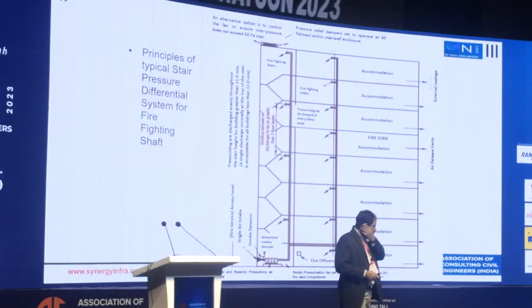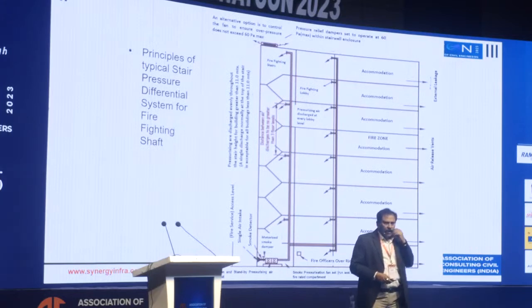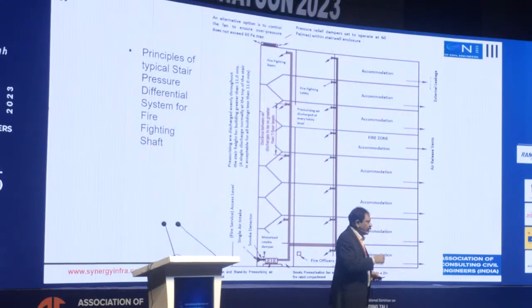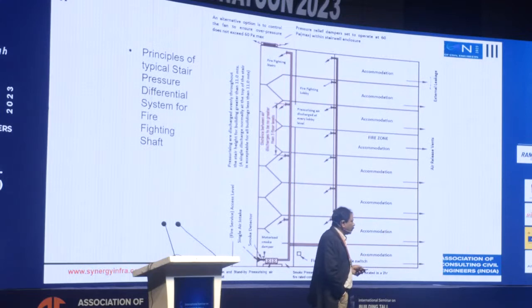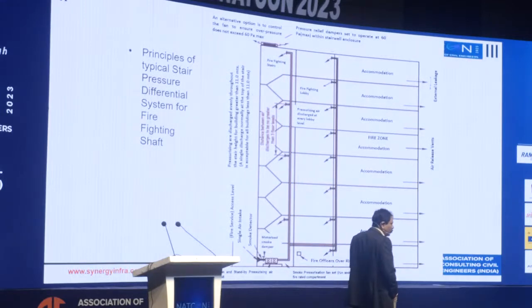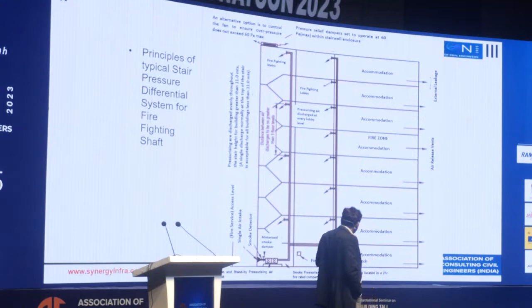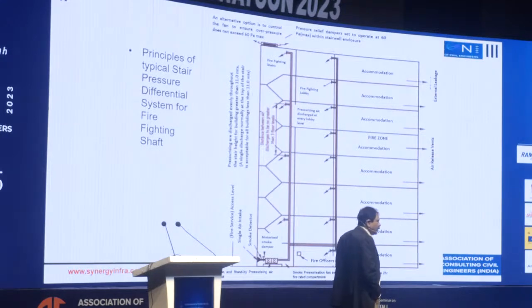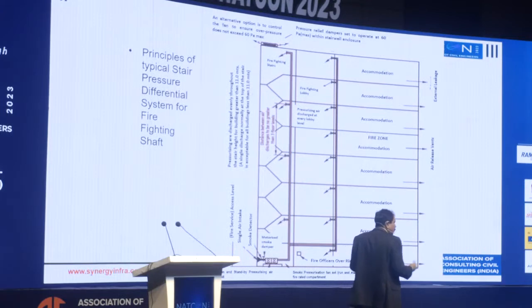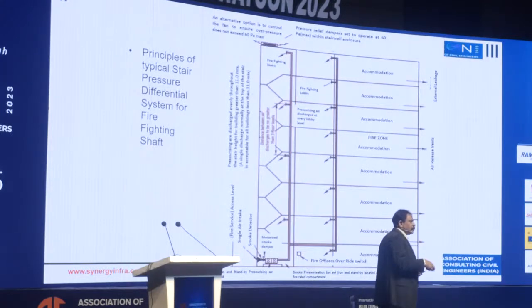Staircase pressurization can be done with single injection or multiple injections, especially in tall buildings with service floors. You may have to inject from service floor levels because you can't pressurize an entire staircase for a 500 meter or 300 meter tall building. So you'll have a fan at the top or bottom, wherever it's open to the air, and the shaft air intake should be kept away from other shafts, because otherwise it may pick up smoke.